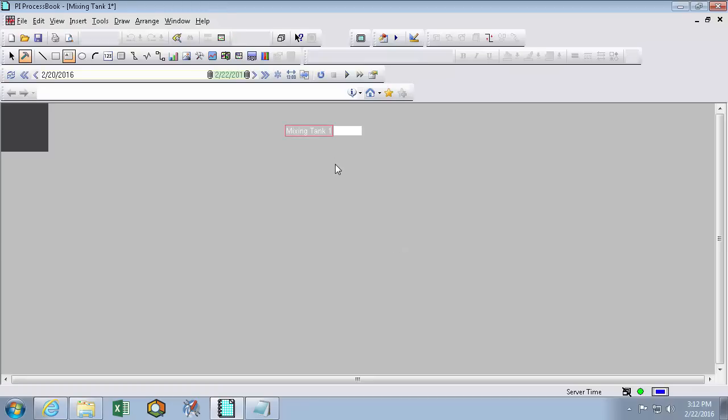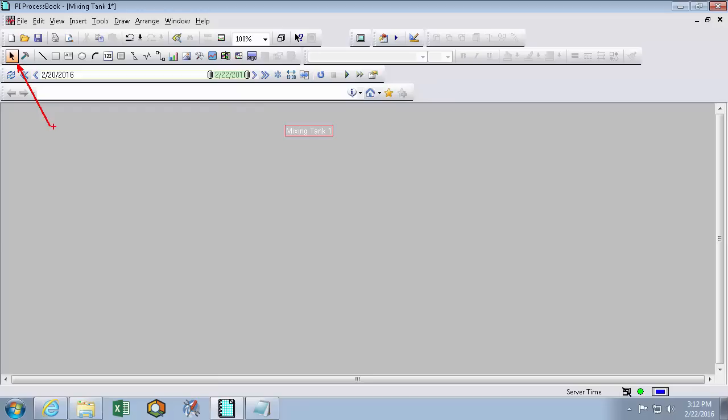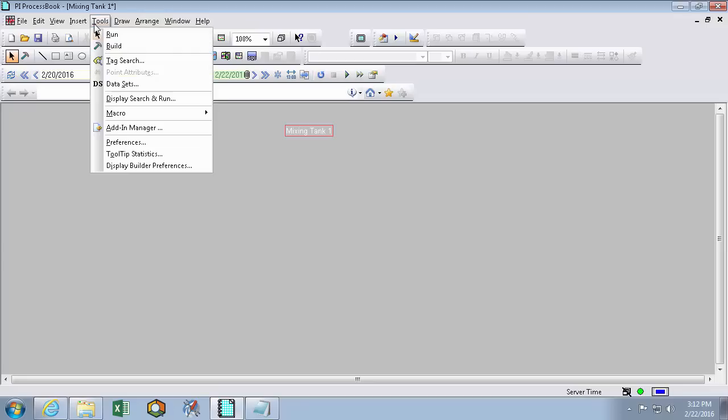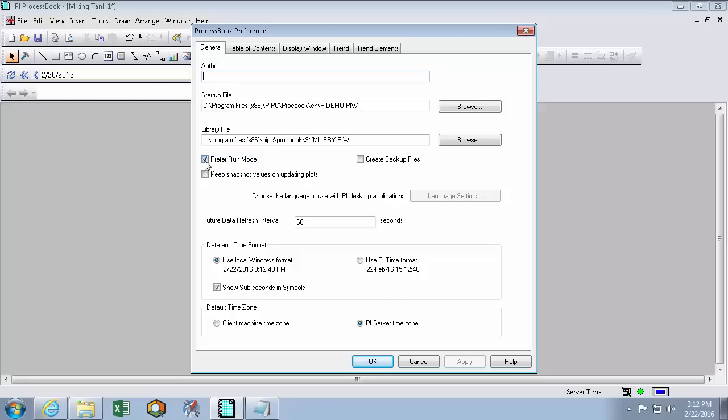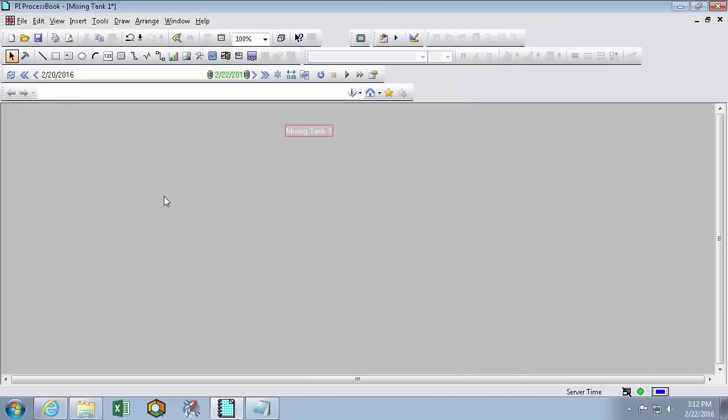So now clicking away, I have the Mixing Tank 1 selected. But you'll notice that I got kicked out of build mode and now I'm in run mode. So there's a default setting set in ProcessBook under Tools Preferences called Prefer Run Mode. And what this does is returns you to run mode after you've created a symbol. Since we're going to plan on being in build mode for quite a while when we build out our display, I'm going to uncheck that. And now we won't have to return to build mode every time we're done dropping a symbol on our display.